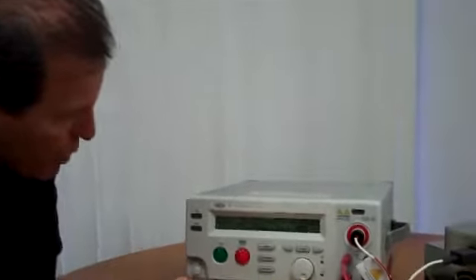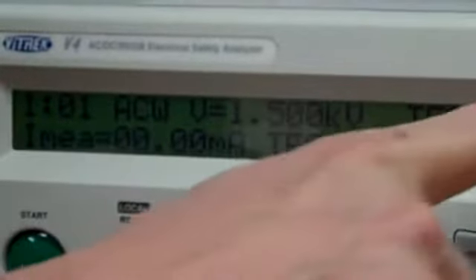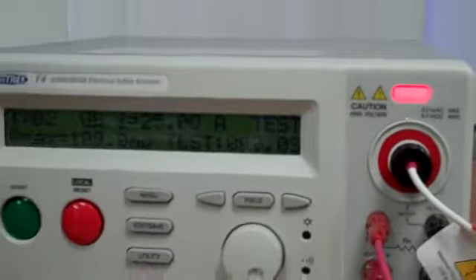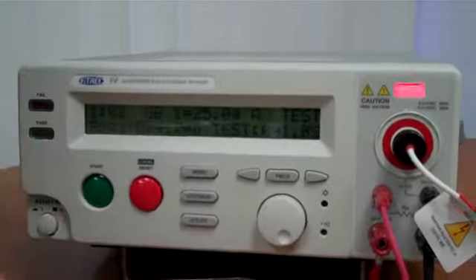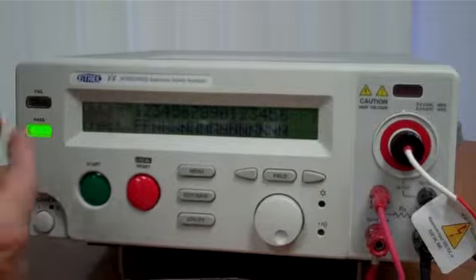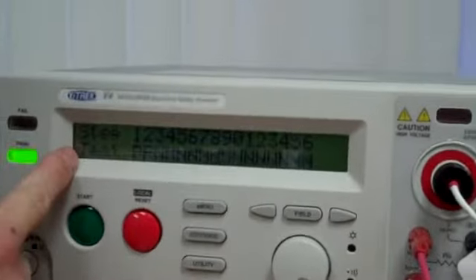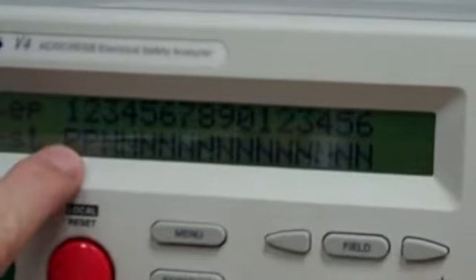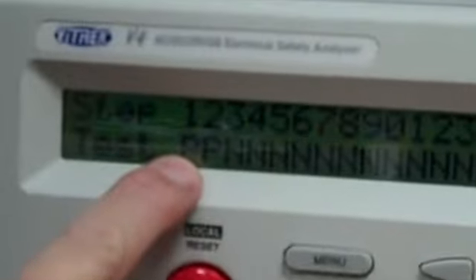If you notice, we're in the edit mode here. If I hit the reset, we clear that, we put it in the ready mode, and then all I have to do is punch the green button to run the test. So here we go. We've got a high voltage warning indicator. You can see the test voltage is counting down for test time. Now we're doing the ground bond test. And then here's our summary screen, where it shows we passed the first 2 steps on this test number 1.